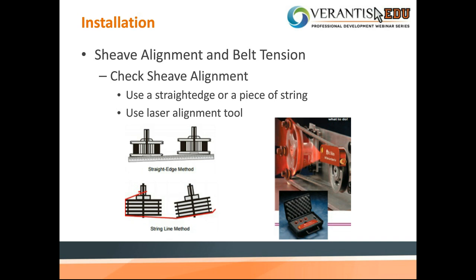And then same thing with the string method below. You see that the piece of string is perfectly aligned with the pulley on the right, but when you go over to the pulley on the left, it's only touching in 1 point. So it's pretty simple, pretty rudimentary. If you don't have a laser alignment tool, this is a great field measurement.